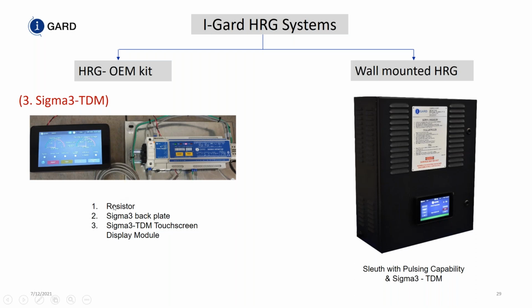The difference is that with the OEM kit, you need to find a place to put the resistor. With the wall-mounted unit, the resistor is integral to this box, and you can typically find space on a wall or on the side of a piece of switchgear to mount it. This is 28 inches by 20 inches and 8 inches deep, so it's very small. We monitor the voltage across the resistor and the current going through the resistor, and you can determine whether there's a fault on the system by those simple means. And we have other relays which mount in a similar footprint.